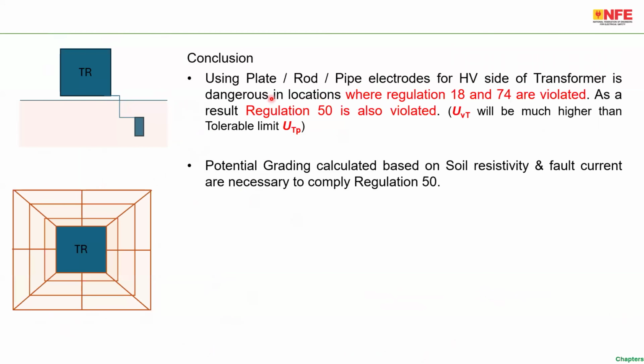Now, conclusion. The simple conclusion is, why I am making this strong statement is, we always have the habit of using plate calculated for some fault current, 13 kiloampere of fault current going through the plate. You need 23 plates in one case, maybe 15 plates in another case, 2 plates in another case where the soil resistivity is very low.